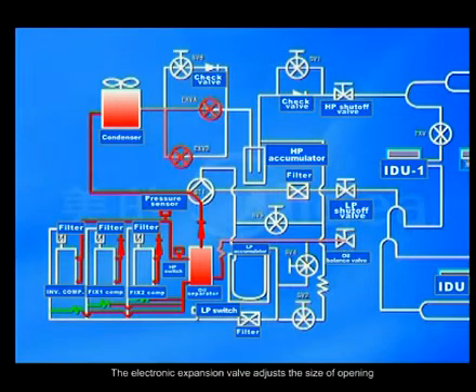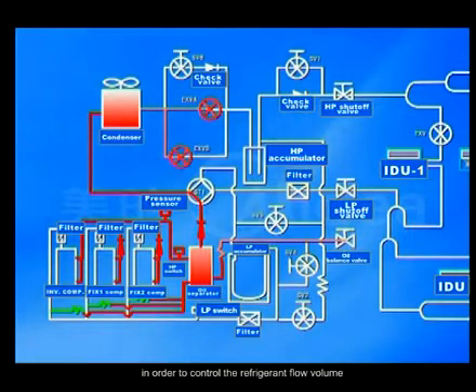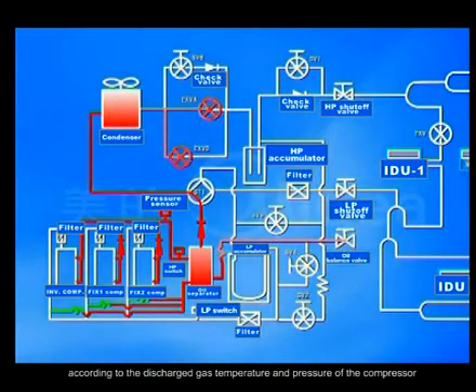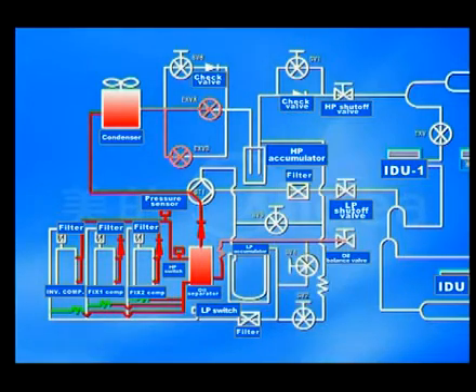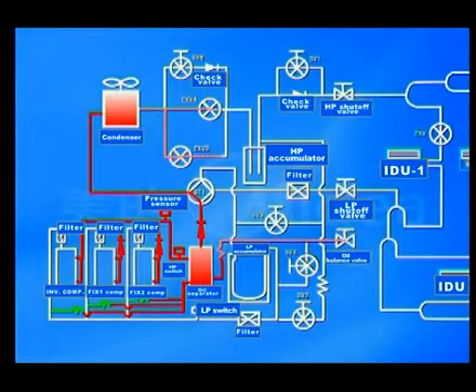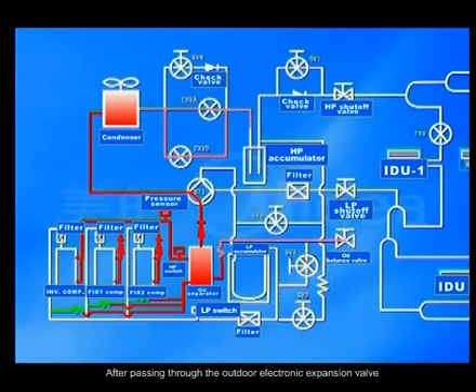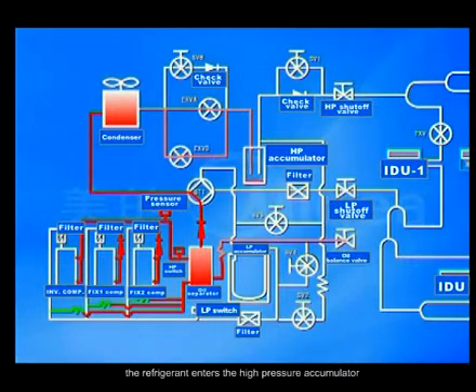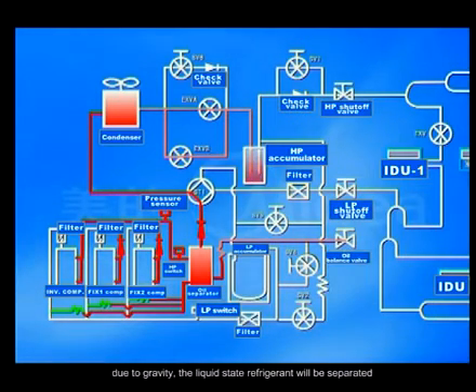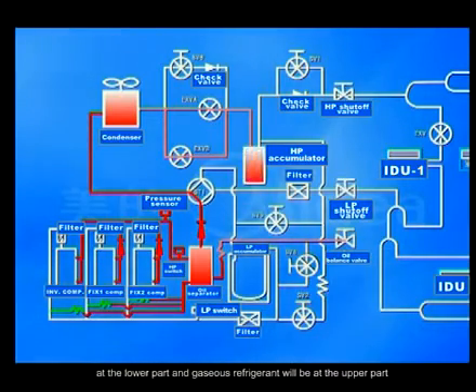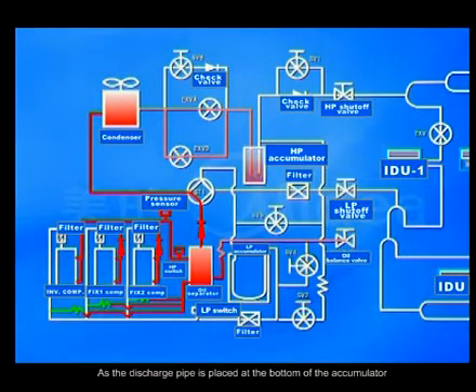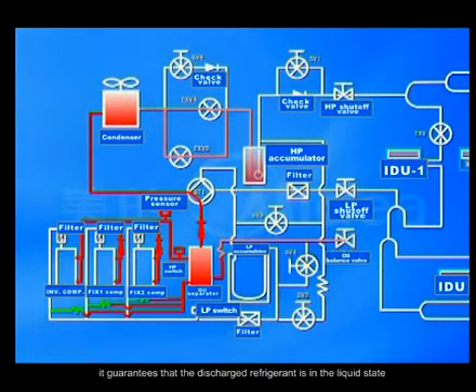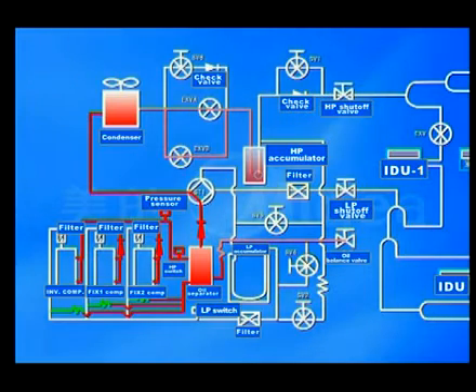The electronic expansion valve adjusts the size of opening in order to control the refrigerant flow volume according to the discharged gas temperature and pressure of the compressor. After passing through the outdoor electronic expansion valve, the refrigerant enters the high-pressure accumulator. Due to gravity, the liquid-state refrigerant will be separated at the lower part, and gaseous refrigerant will be at the upper part. As the discharge pipe is placed at the bottom of the accumulator, it guarantees that the discharged refrigerant is in the liquid state.